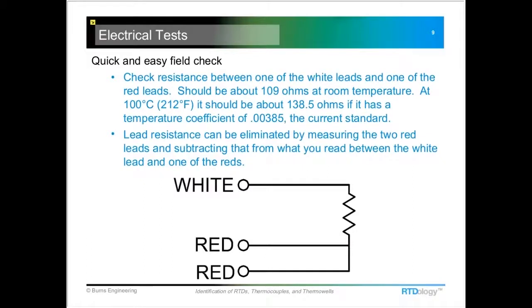And what you want to do is check between, in the case of a three-wire system, you'd want to check between the white lead and one of the red leads. You don't want to use both of them, just one of them, and measure that resistance.